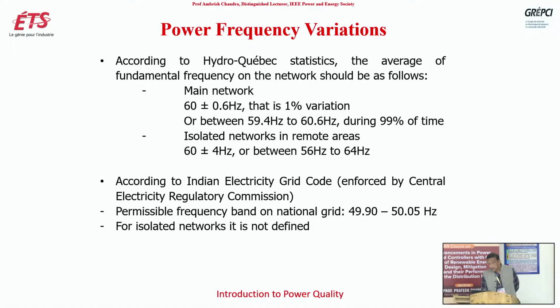According to the Indian Electricity Grid Code, enforced by the Central Electricity Regulatory Commission, the permissible frequency band on the national grid, because you have 50 Hertz, is 49.9 Hertz to 50.05 Hertz. So this is the Indian Electricity Grid Code. For isolated networks, it is not defined. Right now, because 2 years ago I heard that all areas are now connected with the main grid, but I don't know in India. So maybe it is not that important because perhaps there are not many isolated communities in India.